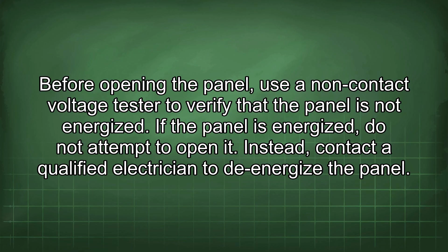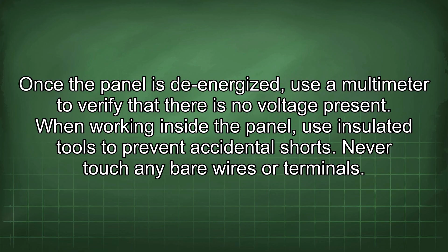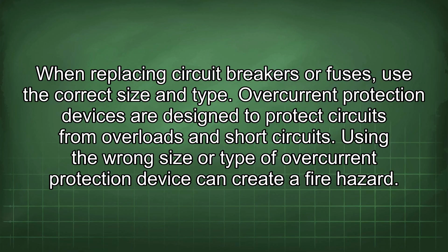Once the panel is de-energized, use a multimeter to verify that there is no voltage present. When working inside the panel, use insulated tools to prevent accidental shorts. Never touch any bare wires or terminals. When replacing circuit breakers or fuses, use the correct size and type. Overcurrent protection devices are designed to protect circuits from overloads and short circuits. Using the wrong size or type of overcurrent protection device can create a fire hazard.